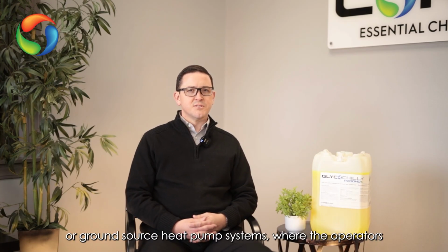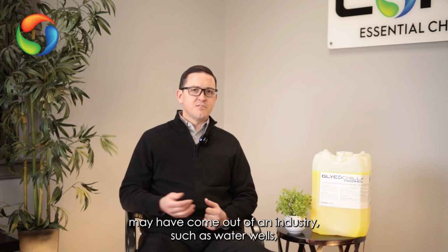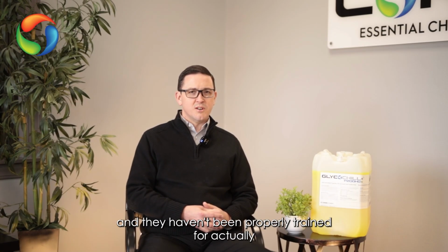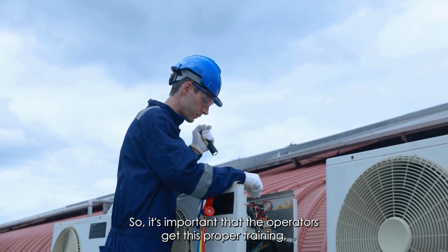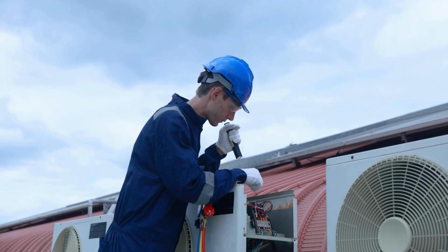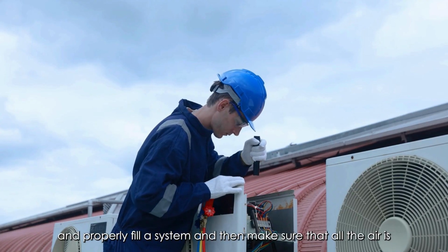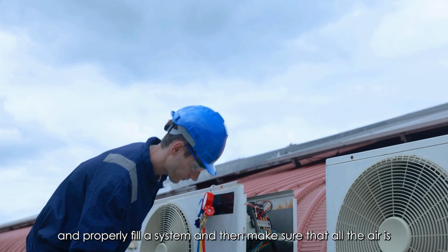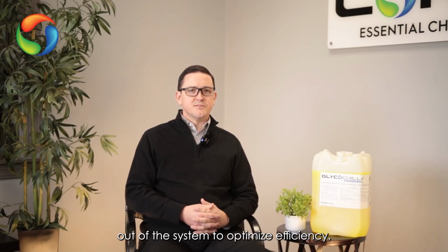We see this issue pop up sometimes even with experienced operators, but a lot of times it's with newer folks to the industry. In industries such as geothermal installation or ground source heat pump systems, operators may have come out of industries such as water wells and haven't been properly trained for installing and maintaining hydronic HVAC systems. So it's important that operators get proper training to learn how to flush and properly fill a system, and make sure all the air is out of the system to optimize efficiency.